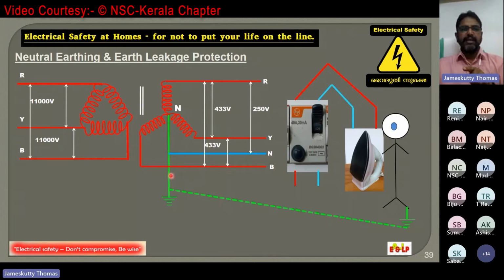It can happen either through improper or loose contact of this neutral earthing, or even because the earthing of our house is not proper. So there are various reasons for this neutral earth voltage. And another thing you must note: if this neutral is loose, your equipment will get higher voltage. That is also another disadvantage. If there is higher voltage, suppose say it is 350 or 400 volt, you must complain to KSEB, because of the loose neutral earthing.